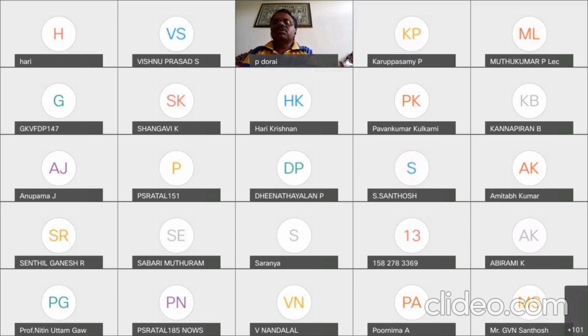And also we have a blood warmer. In the blood warmer, we have a temperature sensor, because once blood is donated by a person, it is stored in the freezer to keep the RBCs and WBCs in good form. Prior to infusion into the patient, this blood has to be brought to the body temperature of 37 degrees centigrade. That's why we use a blood warmer. If it is heated too much beyond 37 degrees centigrade, the blood constituents RBC and WBC will rupture and be rendered useless. To prevent that, we have a temperature sensor. Based on the temperature sensor, the current to the heating element is switched on and off automatically.